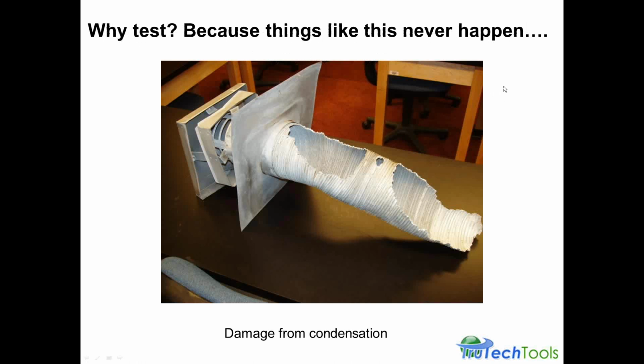Here's another issue. We assume everything's running okay, and this was a vent system that was damaged due to condensation. The water condensed inside the vent and mixed with the flue gas, with the nitric acid and sulfur dioxide in the flue gas, causing it to actually etch and eat through this metal vent material. So the vent was no longer functioning as a vent because it had been eaten through by a combination of condensation in the vent line, which is probably due to not enough draft or some other cause, or maybe an improper installation with this type of material.